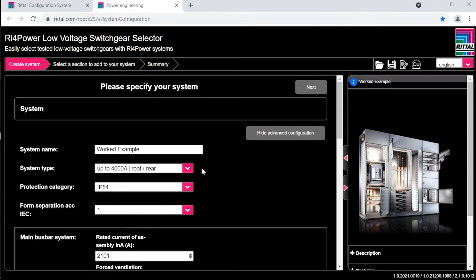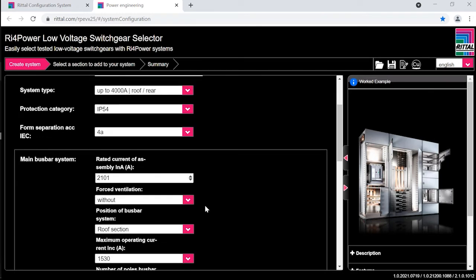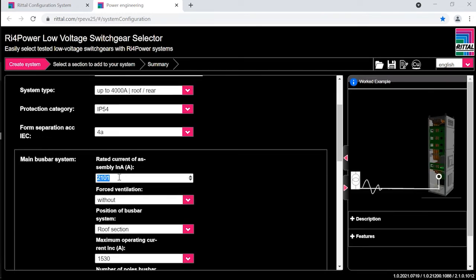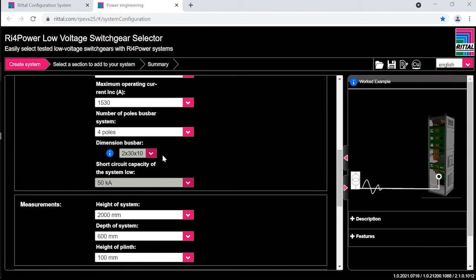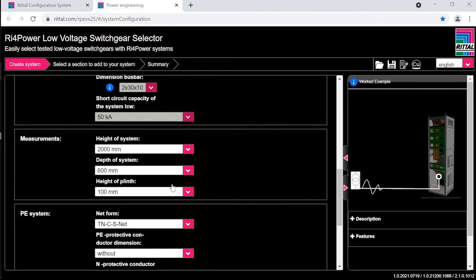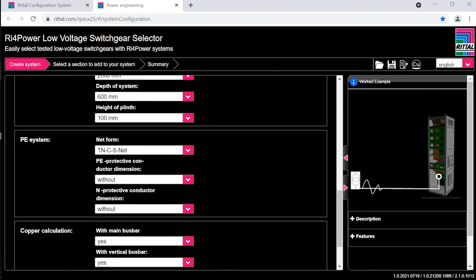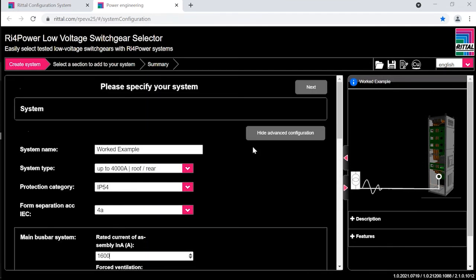So we've got the title and the form of separation. This is the segregation of the bus bars from the components and the terminals. For the rating of the bus bars, we said 1600 amps, no forced ventilation, 4 poles. The bus bars in the roof are 2 by 30 by 10, which is good for 50 kA for 1 second. That's the ICW rating, and it's confirming the size. So I'm happy with that, and we'll go to the next page.